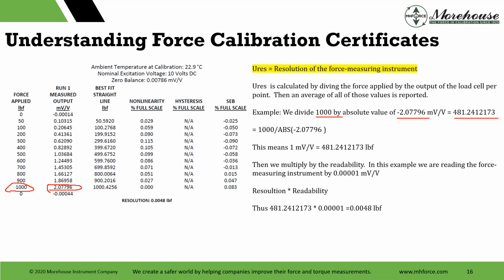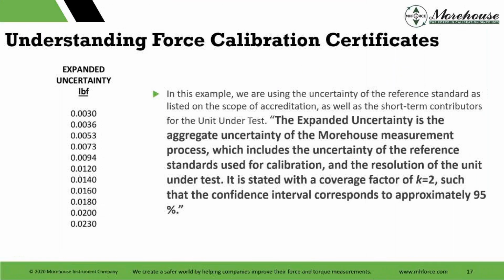So you take 1,000, take the absolute value. I recommend it because if you had compression and a negative output in compression, this one has tension. I'm showing you what would happen here and why we do it, because if you had something negative, it would pop up negative. But anyway, we divide it. 1 millivolt then equals 481.24 pounds. From there, if we want to find the resolution, we multiply by the readability. This load cell in particular reads one count at the 5th decimal place, millivolt per volt. Multiply this, and we get 0.0048 pounds.